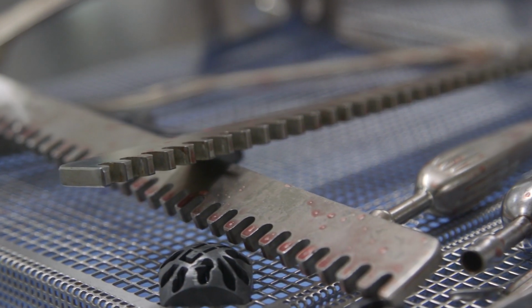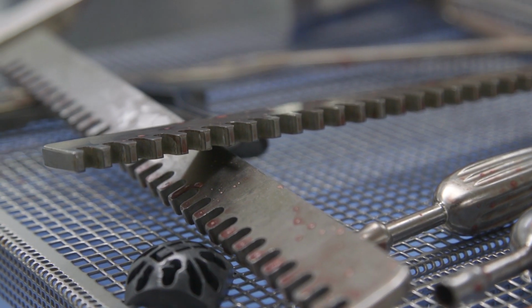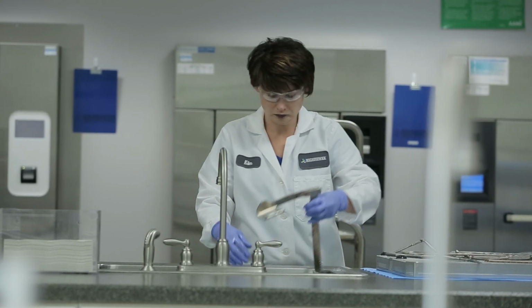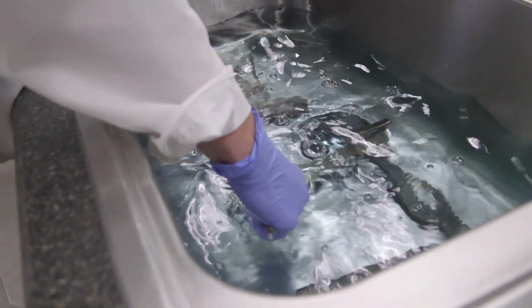Nowadays, medical devices are becoming more complex and smaller, which is excellent for patient care, but they tend to have more crevices, more spots for potential contamination. Cleaning a device is just as important as sterilizing the device. You have to remove the bioburden like dried blood in order for the device to be properly sterilized.